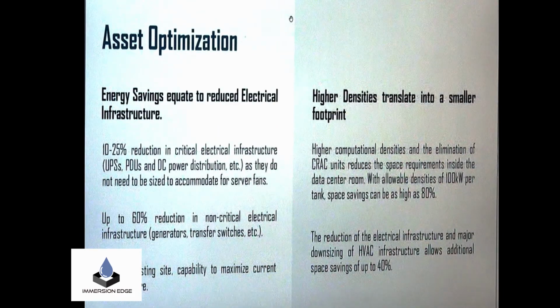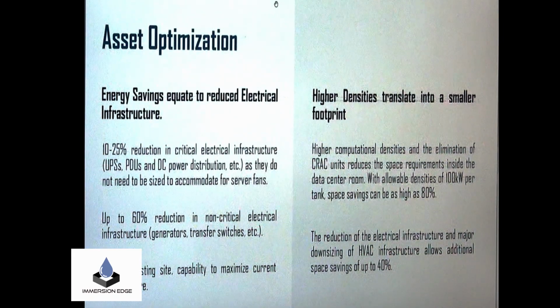So again we've covered a couple of things already in the electrical. You have a 10 to 25% reduction in critical electrical infrastructure with your UPSs, your PDUs, the DC power distribution - they don't need to be sized to accommodate for server fans. Again, 60% reduction in non-critical electrical infrastructure with your generators and transfer switch. So everything starts chipping down, and if it's in an existing site, the capability to maximize your current infrastructure is important.